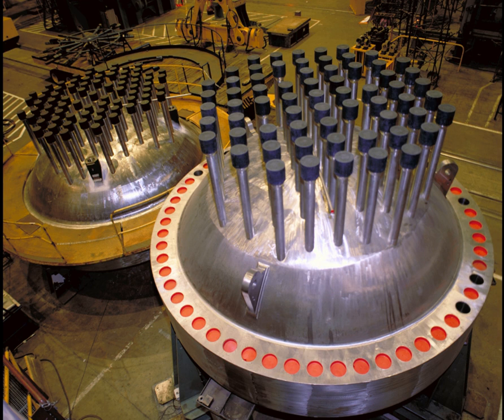The reactor control rods, inserted through the reactor vessel head directly into the fuel bundles, are moved for the following reasons: to start up the reactor; to shut down the primary nuclear reactions in the reactor; to accommodate short-term transients such as changes to load on the turbine. The control rods can also be used to compensate for nuclear poison inventory and fuel depletion, though these effects are more usually accommodated by altering the primary coolant boric acid concentration. In contrast, BWRs have no boron in the reactor coolant and control reactor power by adjusting the reactor coolant flow rate.